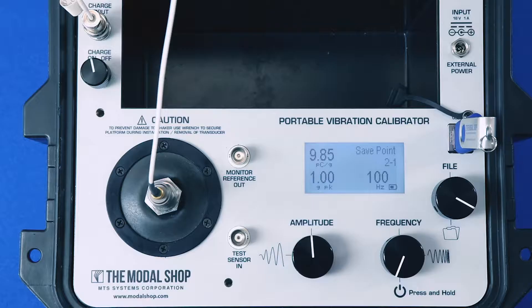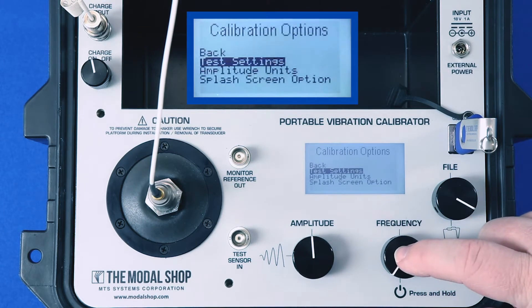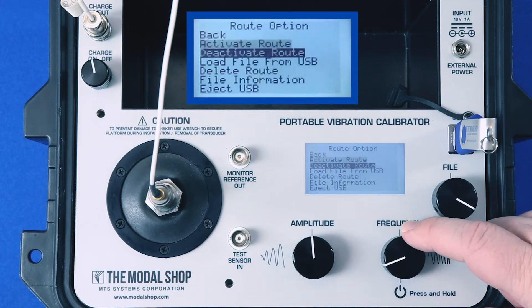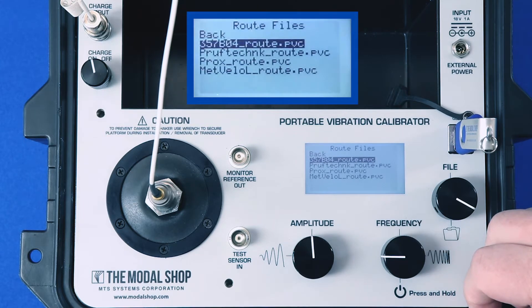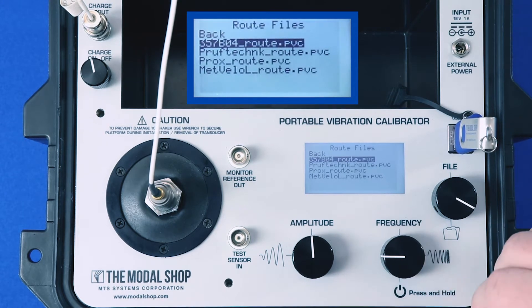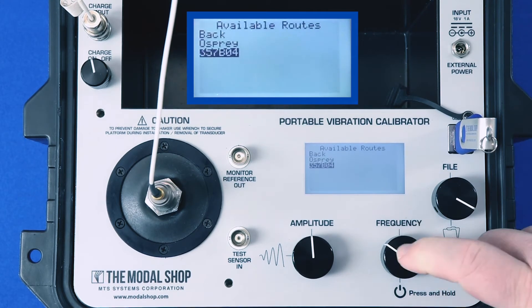The next step in calibrating the 357B04 is to load our pre-programmed step sine test with pass/fail notification and activate it. I use the frequency dial to highlight the test settings, go to the cal route function, and load a file from my USB that I've plugged into the top of the calibrator. The calibrator reads the USB and gives me a list of available cal routes. I'll choose the 357B04.